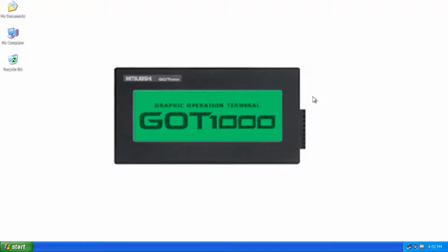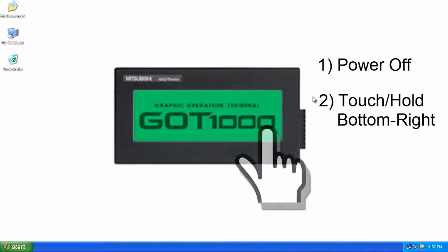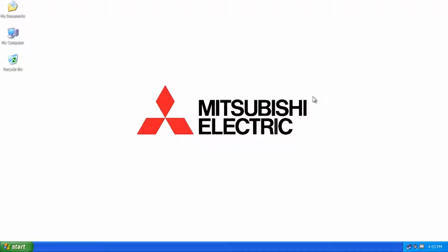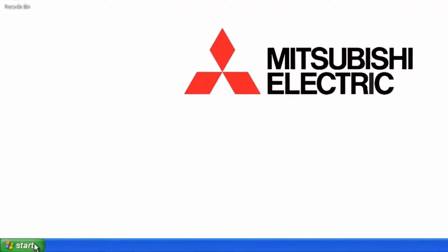The solution really is to unplug the power and then put your finger on the bottom right-hand corner of the terminal and then turn the power back on. From there you'll be able to install the OS including the communication driver from the Mitsubishi software. And the software is GT Works 3. So let me give you a quick demonstration of how to do that.